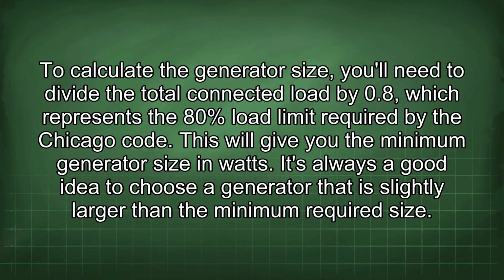To calculate the generator size, you'll need to divide the total connected load by 0.8, which represents the 80% load limit required by the Chicago Code. This will give you the minimum generator size in watts.